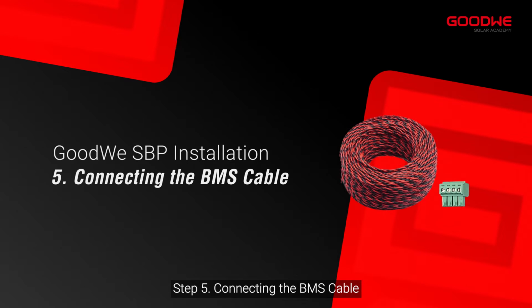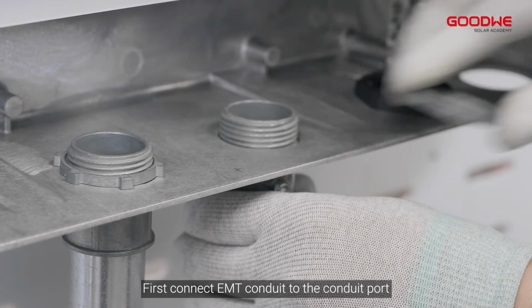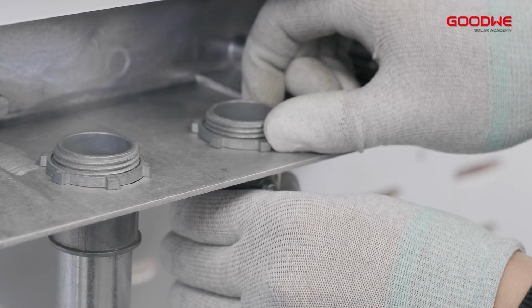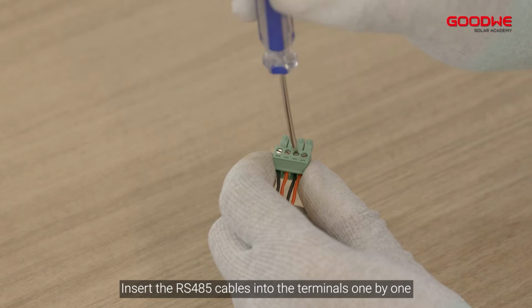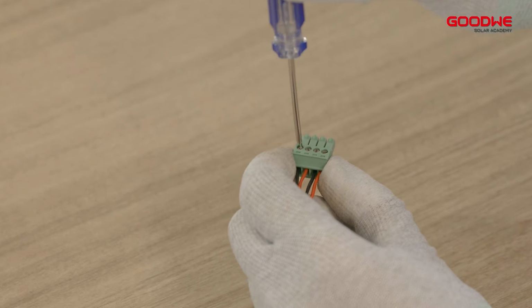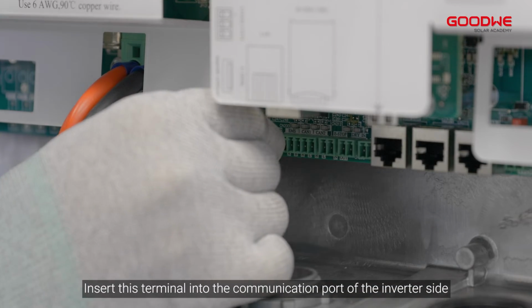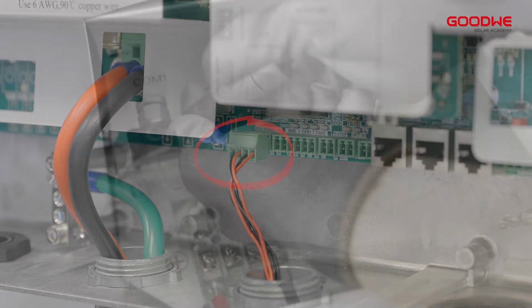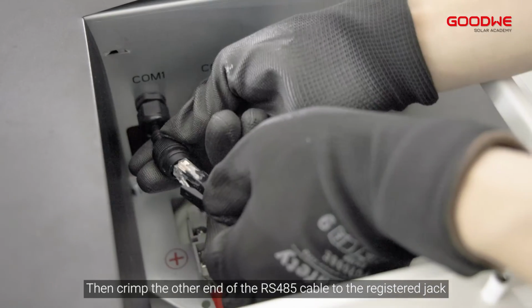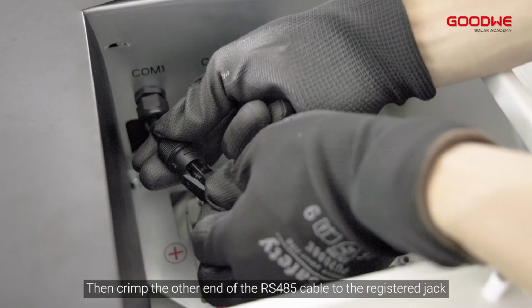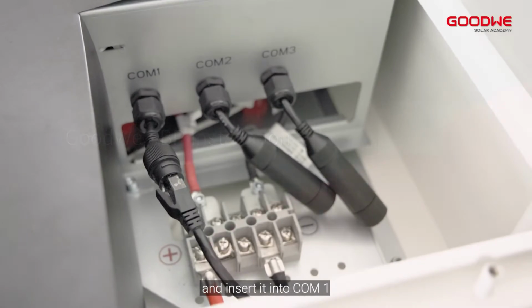Step 5. Connecting the BMS cable. First connect EMT conduit to the conduit port. Insert the RS485 cables into the terminals one by one. Insert this terminal into the communication port of the inverter side. Then crimp the other end of the RS485 cable to the registered jack, and insert it into COM1.